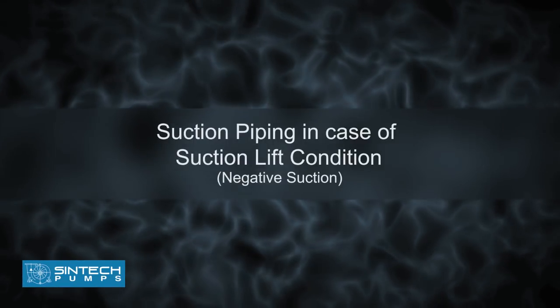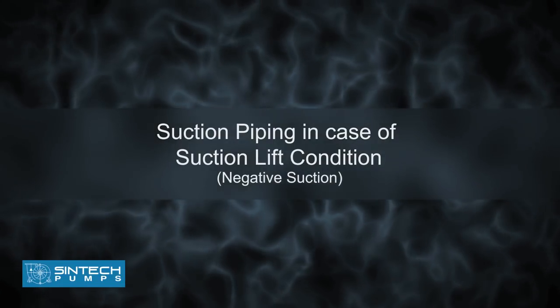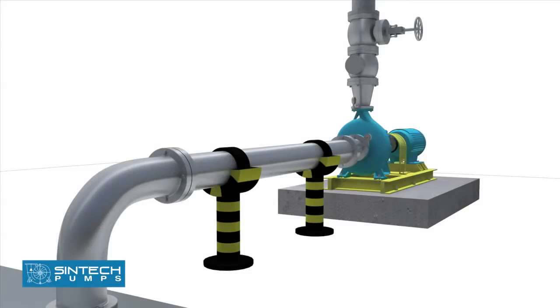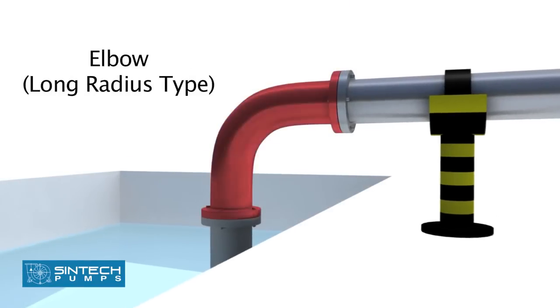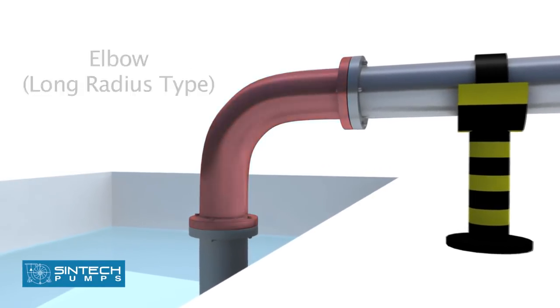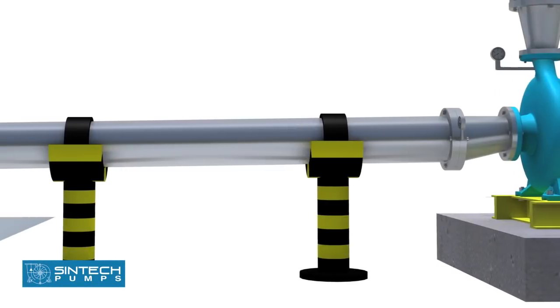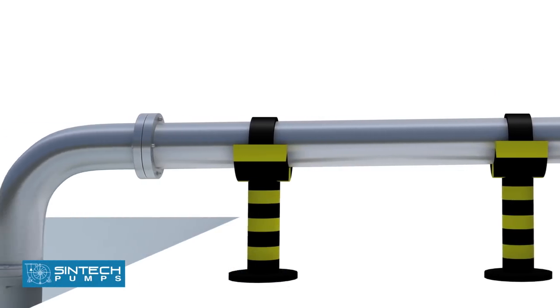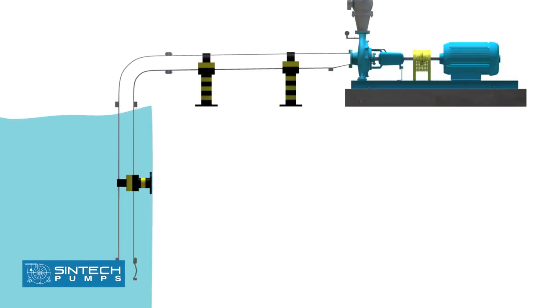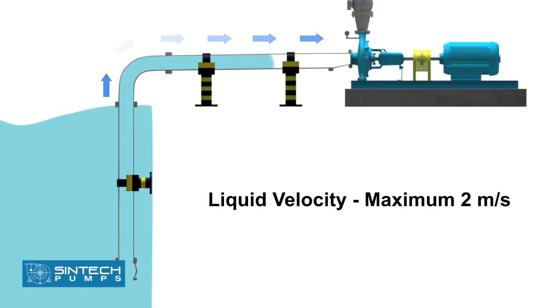Suction Piping in case of suction lift condition, Negative Suction. The piping run and the connection fittings should be properly aligned and supported separately. The elbow should be of long radius type. All suction piping must be airtight. The suction pipe should be sized to ensure the liquid velocity of not more than 2 meters per second.